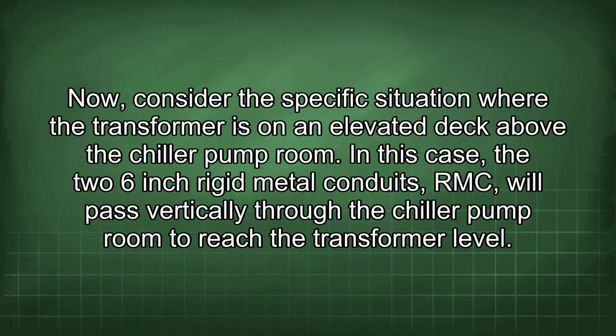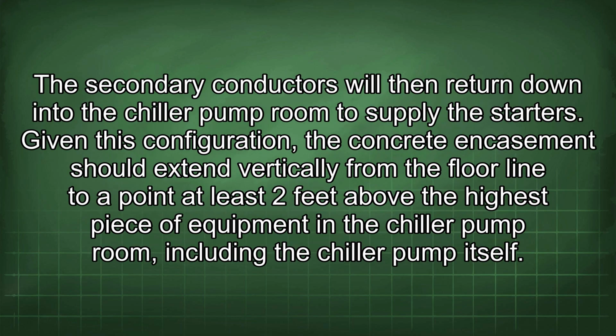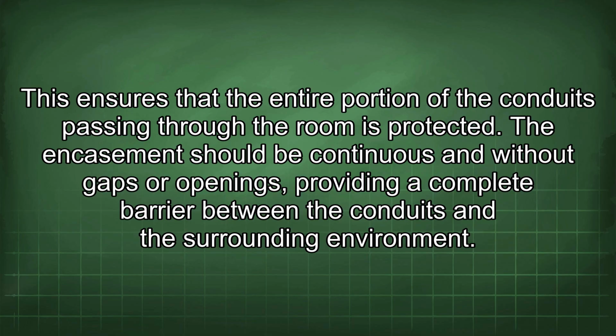Now consider the specific situation where the transformer is on an elevated deck above the chiller pump room. In this case, the two 6-inch rigid metal conduits, RMC, will pass vertically through the chiller pump room to reach the transformer level. The secondary conductors will then return down into the chiller pump room to supply the starters. Given this configuration, the concrete encasement should extend vertically from the floor line to a point at least 2 feet above the highest piece of equipment in the chiller pump room, including the chiller pump itself. This ensures that the entire portion of the conduits passing through the room is protected.